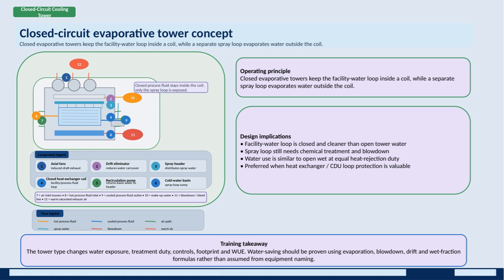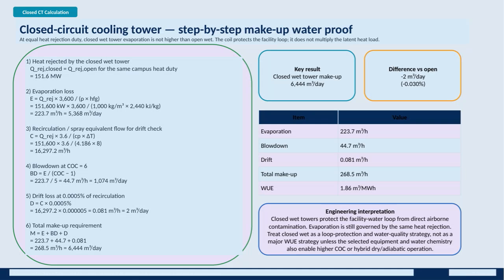Key flow paths include hot process fluid entering, cool fluid exiting, spray water circulating, blowdown for water discharge, and warm air being exhausted. Overall, the closed-circuit cooling tower offers a controlled, efficient approach to heat rejection with clear benefits for sensitive data center cooling applications. Let's go through the calculations for the closed-circuit cooling tower, focusing on makeup water requirements.